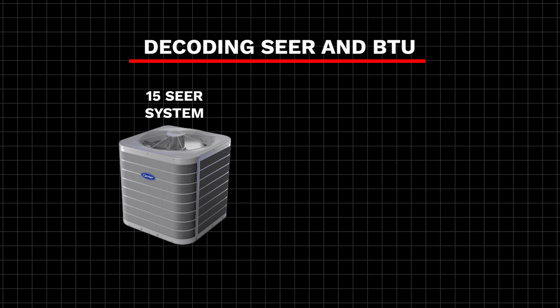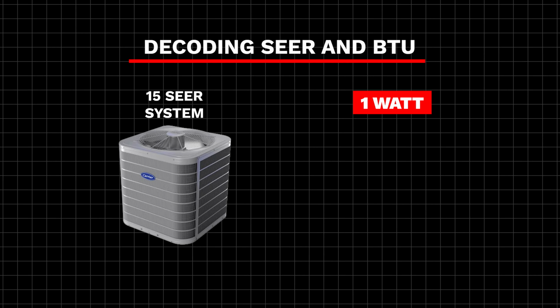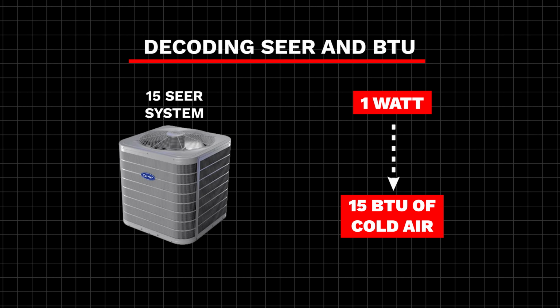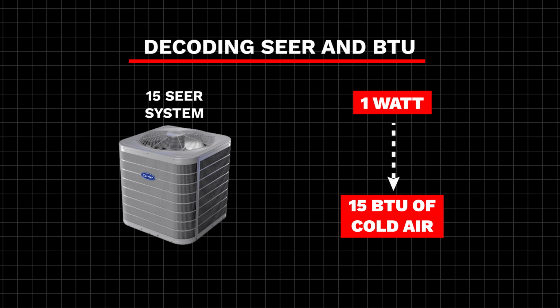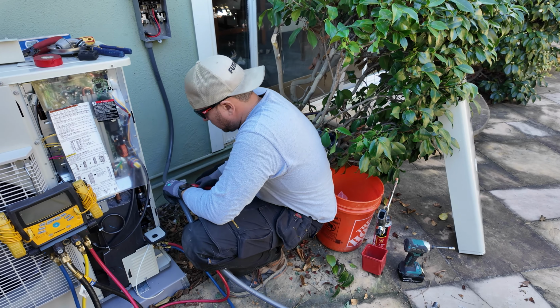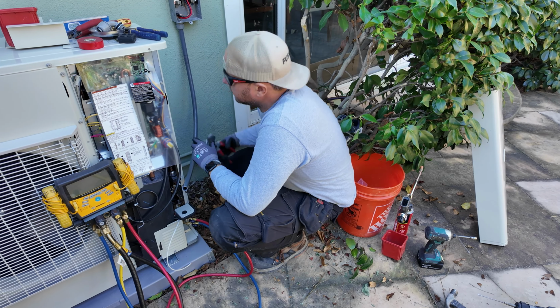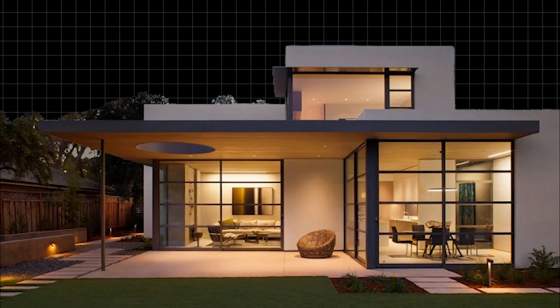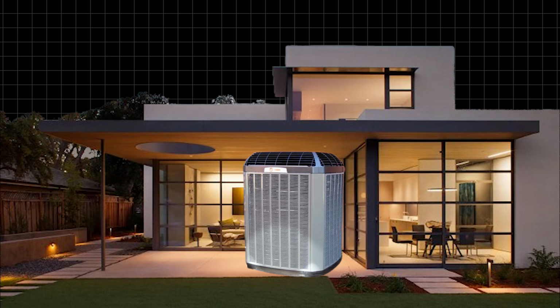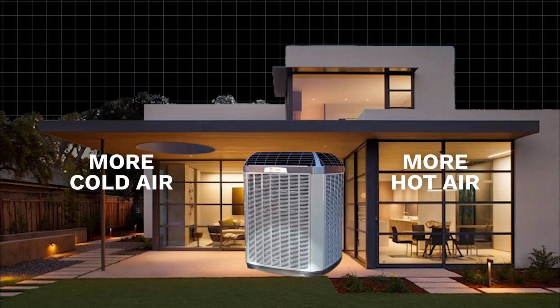What does that number actually mean? It means that, let's say with a 15 SEER system, for each watt of energy, your system is producing 15 BTUs of cold air. BTU is British Thermal Unit, the unit we use to count the amount of heat. So swapping your system from low efficiency to high efficiency means that for the same amount of energy used in your house, your high efficiency system will provide more cold air or more hot air. That's it.